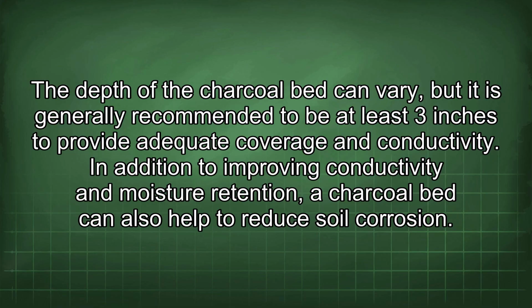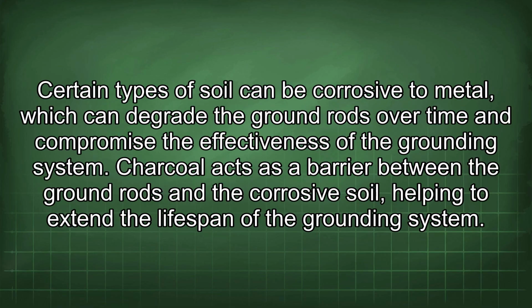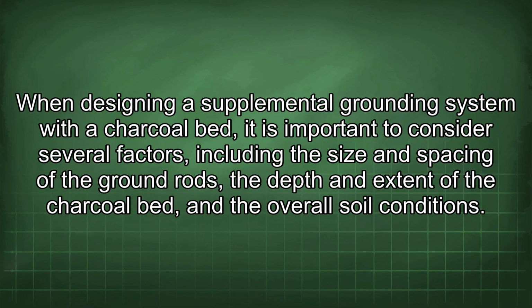In addition to improving conductivity and moisture retention, a charcoal bed can also help to reduce soil corrosion. Certain types of soil can be corrosive to metal, which can degrade the ground rods over time and compromise the effectiveness of the grounding system. Charcoal acts as a barrier between the ground rods and the corrosive soil, helping to extend the lifespan of the grounding system.